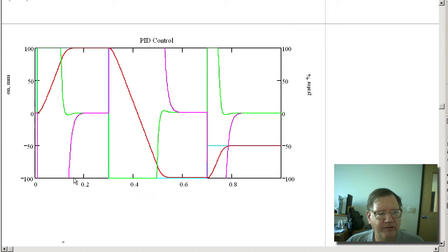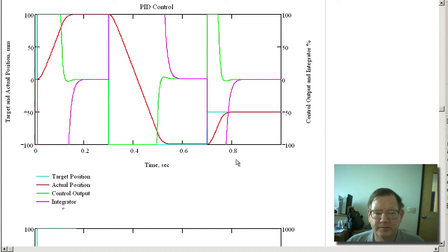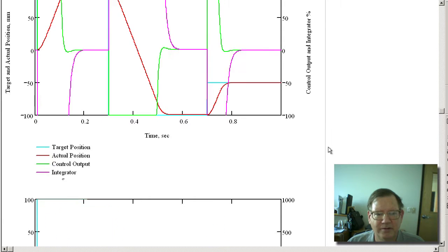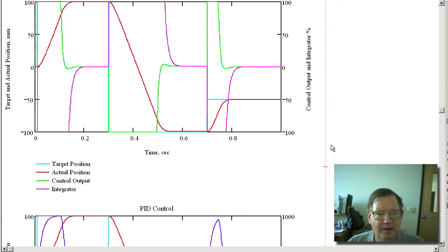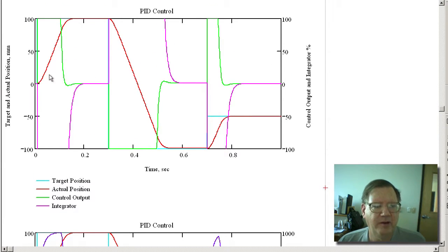So here is the response. This is the position response. We can see the target position does a step up to 100 millimeters. And the actual position goes up to 100 millimeters and doesn't overshoot. The control output saturates at 100%. And that's due to the step jump. And you can see the integrator winds down and then it winds back up to zero. And that's due to the limiting function.